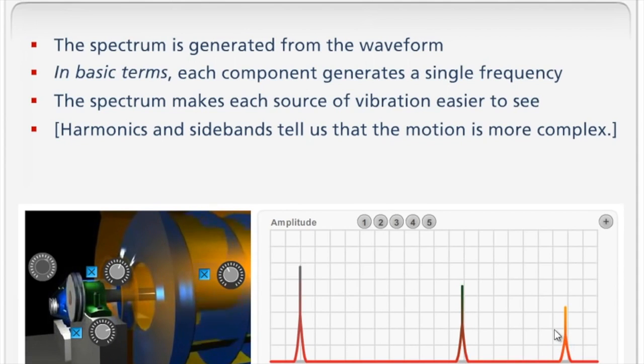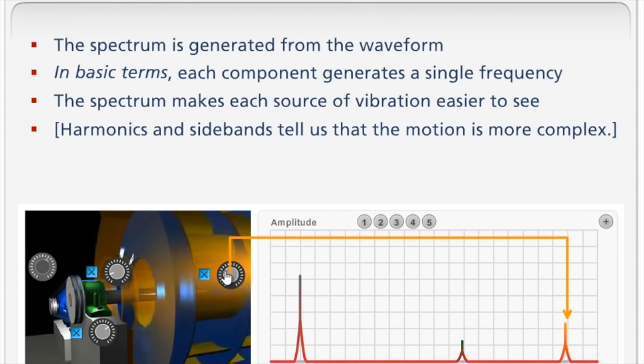If you look, and I didn't line it up very well, but this green vibration is never exactly 9x, or 10x, or 3x. It's always three point something, five point something, seven point something. It always works out that way. But the beauty of all this is that there's the vibration from the shaft, there's the vibration from the bearing, and there's the vibration from the fan.